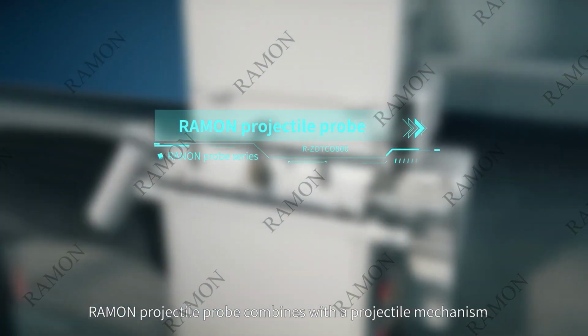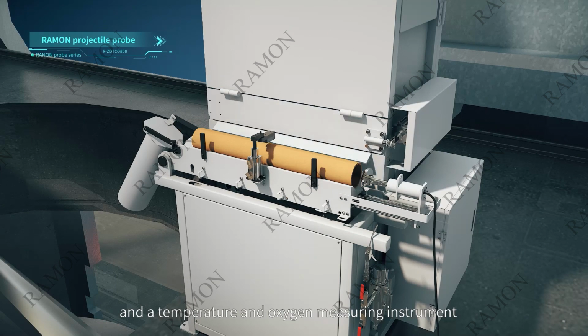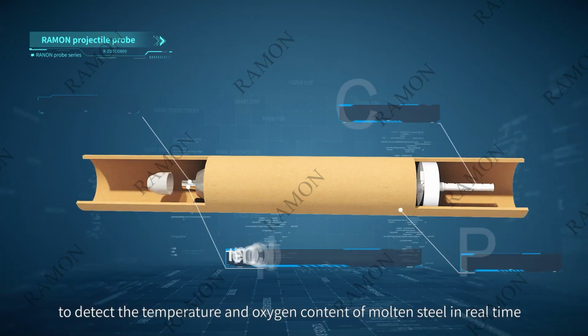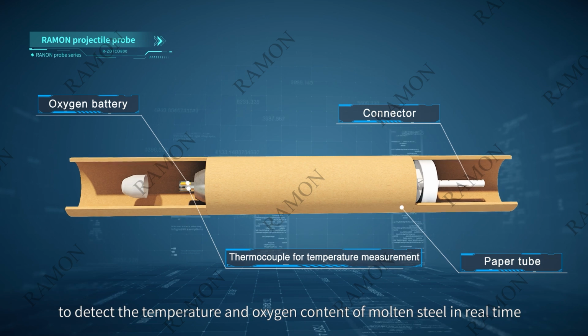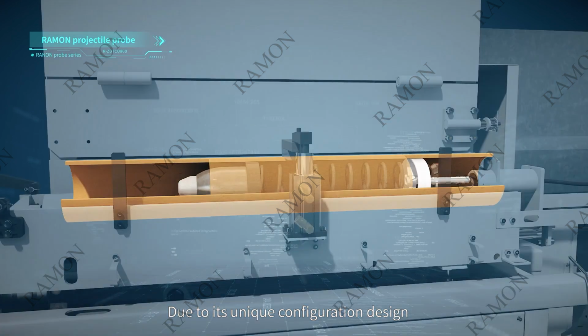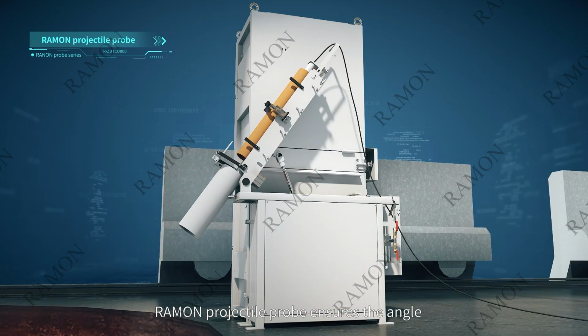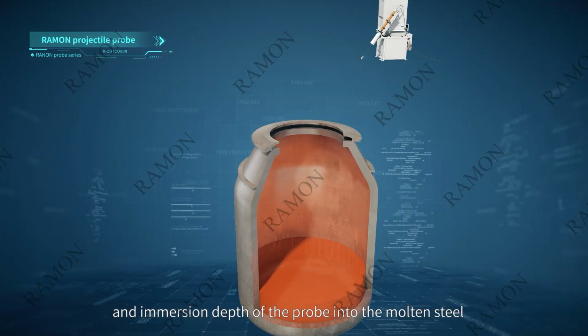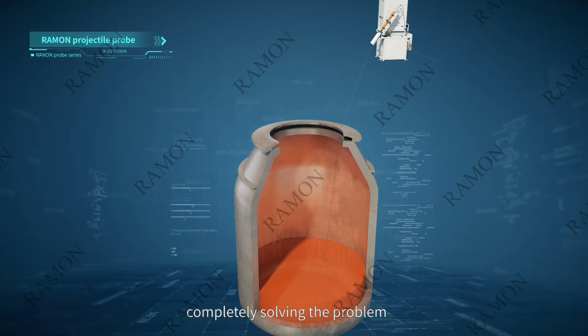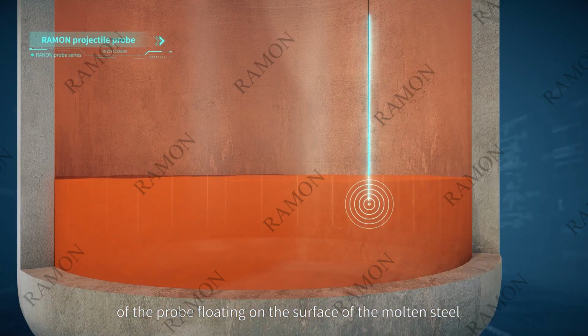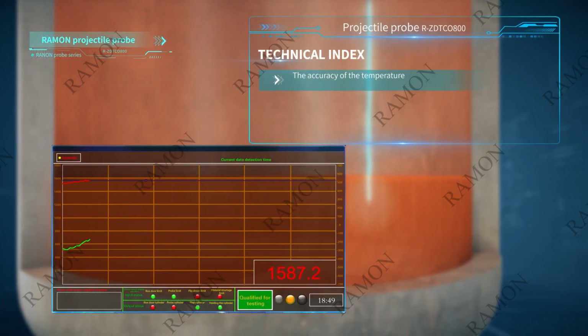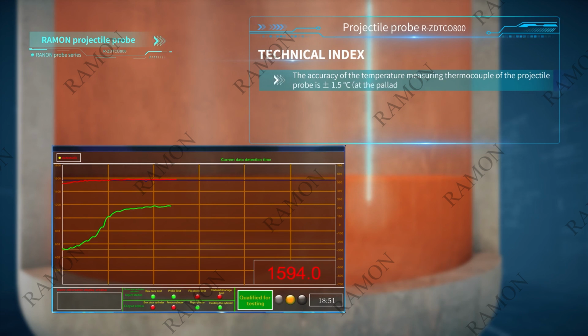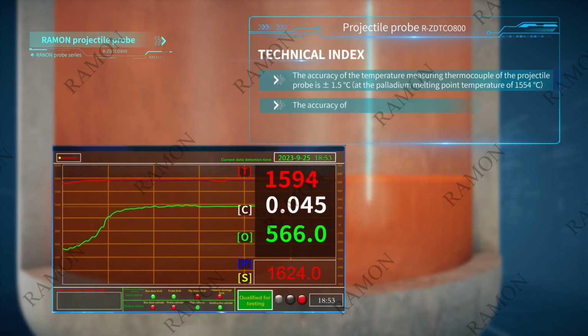RAMON projectile probe combines with the projectile mechanism and the temperature and oxygen measuring instrument to detect the temperature and oxygen content of molten steel in real time. Due to its unique configuration design, the RAMON projectile probe ensures the angle and the immersion depth of the probe into the molten steel, completely solving the problem of the probe floating on the surface of the molten steel. The accuracy of the temperature measuring thermocouple of the projectile probe is plus minus 1.5 degrees Celsius. The accuracy of the oxygen potential is plus minus 3 mV, and the success measurement rate is larger than 98%.